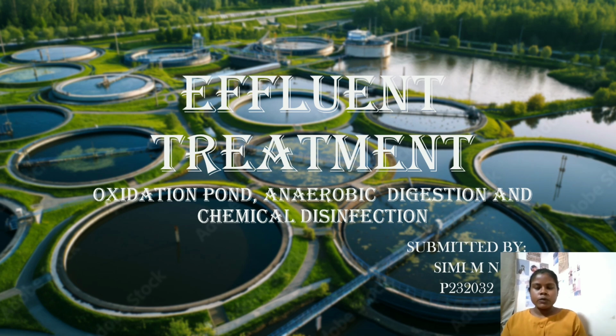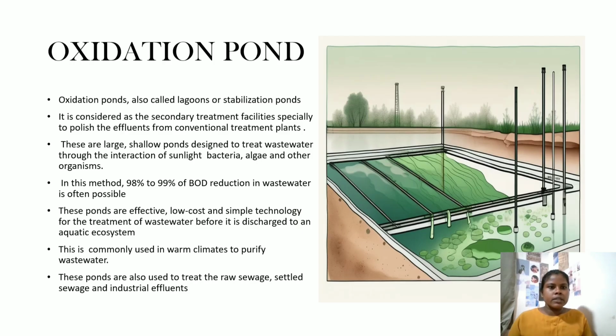So there are three types of methods used in this process. That is oxidation pond, anaerobic digestion, and chemical disinfection. So the oxidation pond is a secondary treatment method. These are large shallow ponds designed to treat wastewater through interaction of sunlight, bacteria, algae, and other organisms. These ponds are commonly used in warm climates, and are also used to treat raw sewage, settled sewage, and industrial effluents.